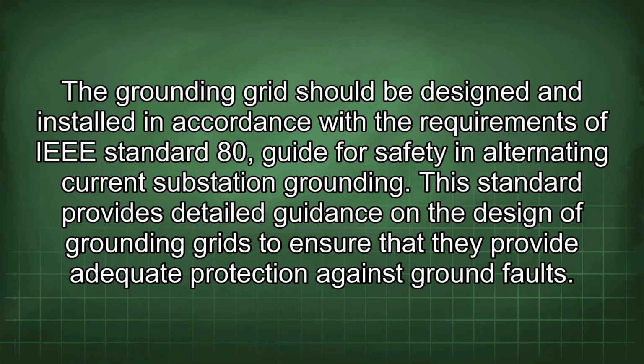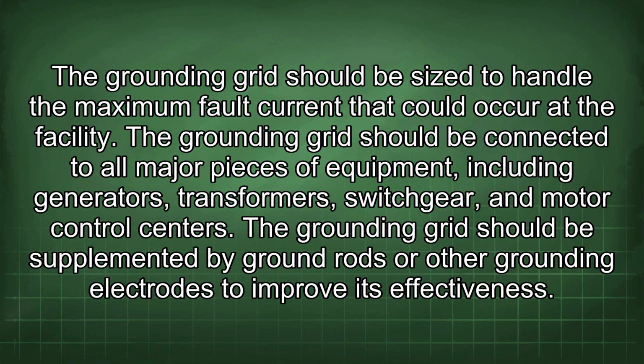The grounding grid should be designed and installed in accordance with the requirements of IEEE Standard 80, Guide for Safety in Alternating Current Substation Grounding. This standard provides detailed guidance on the design of grounding grids to ensure that they provide adequate protection against ground faults. The grounding grid should be sized to handle the maximum fault current that could occur at the facility. The grounding grid should be connected to all major pieces of equipment, including generators, transformers, switchgear, and motor control centers. The grounding grid should be supplemented by ground rods or other grounding electrodes to improve its effectiveness.